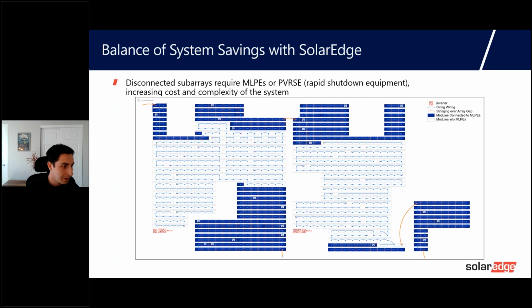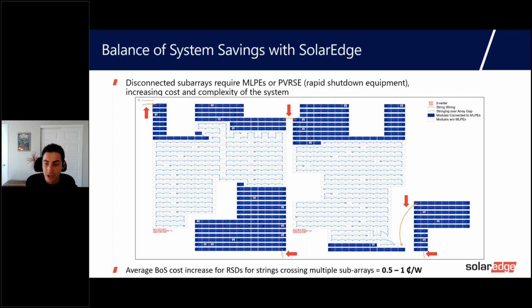If you'll go forward, Kleber, I just wanted to highlight where the strings are crossing gaps in the array. Any module connected to those inverters is going to need to be connected to MLPE. And so when we look at the average increased cost for using MLPEs or PVRSE, there's a variety of strategies. Over 5 case studies, we're seeing an average cost of 0.5 cent to 1 cent per watt, strictly on the MLPE or PVRSE side of things.